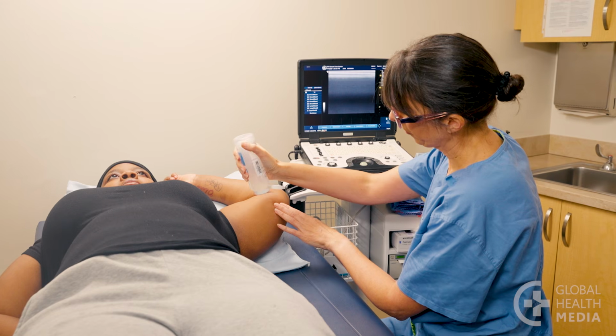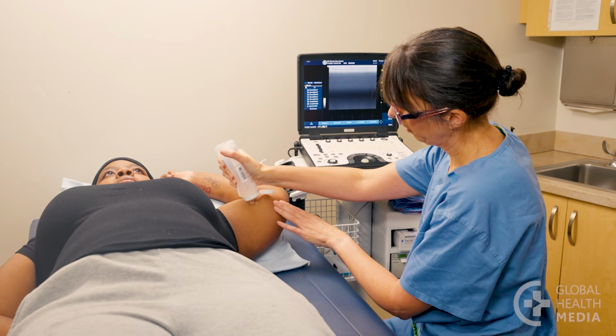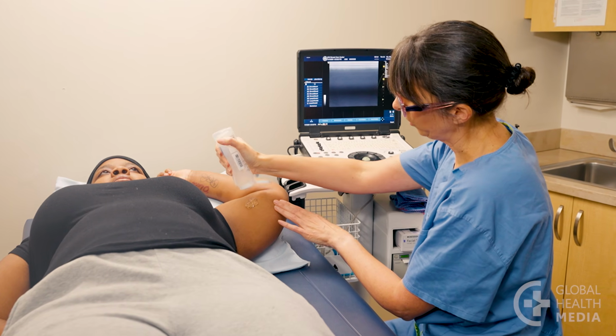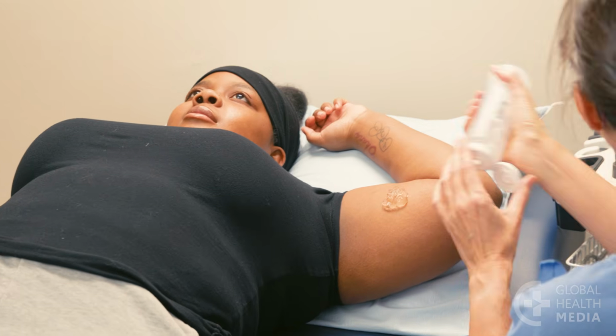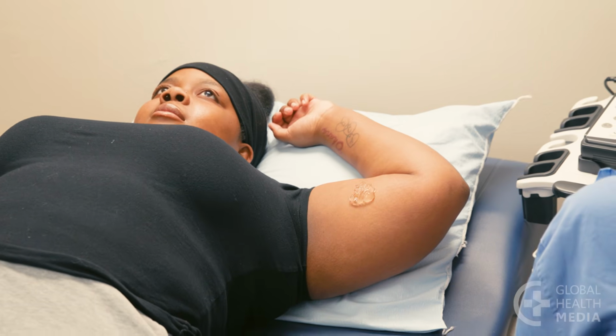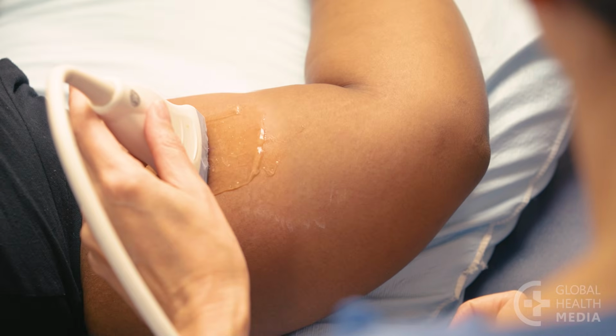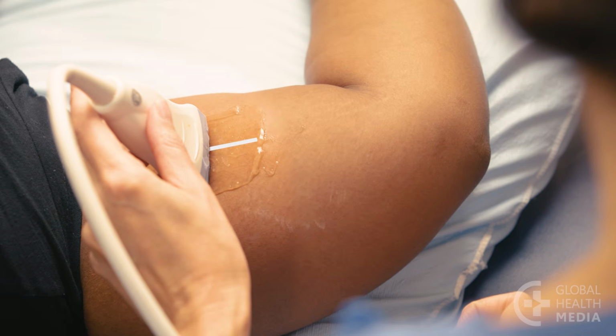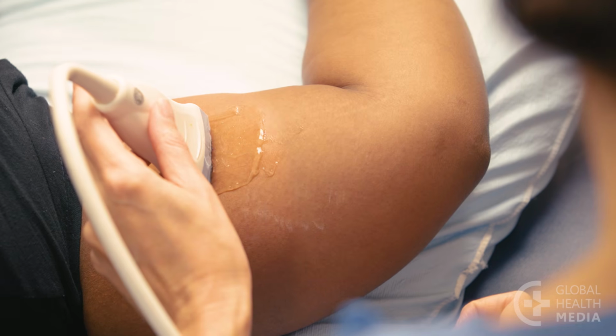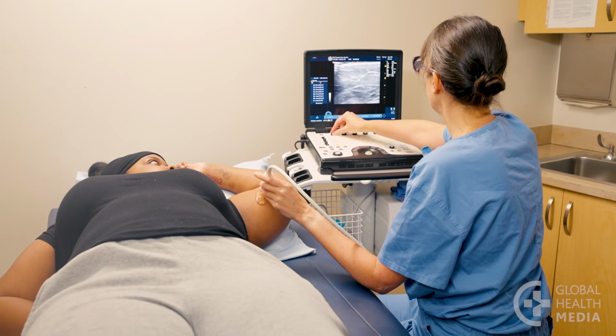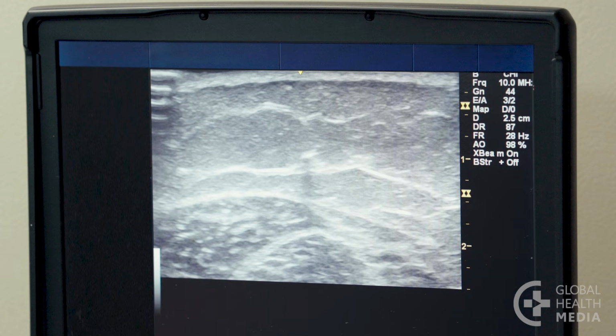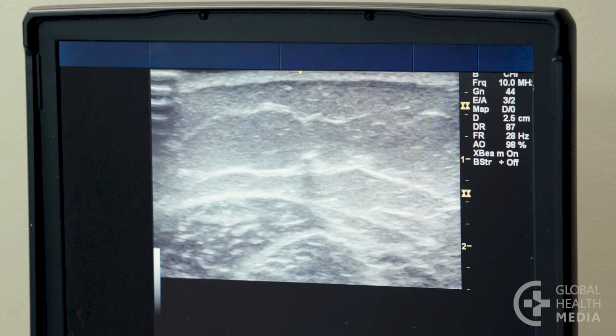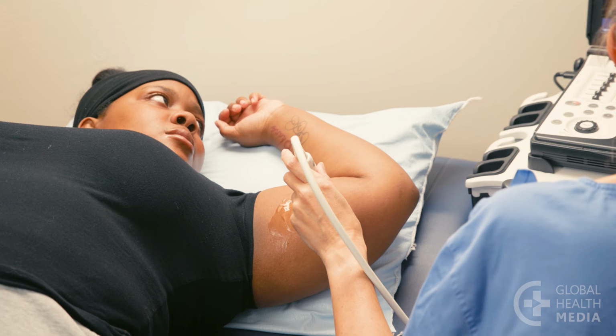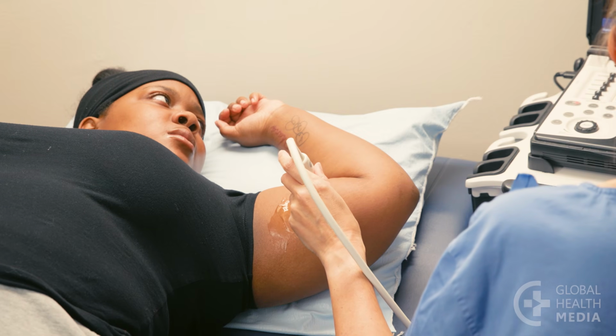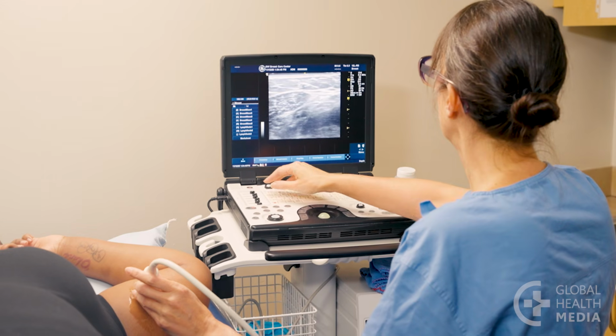Now, locate the implant. Start by placing gel on the skin at the site of the insertion scar. Hold the probe lightly and perpendicular to the usual position of the implant. Then, adjust the frequency to the highest setting to get the clearest image. Move the probe very slowly back and forth. Here's what we're seeing on the screen.